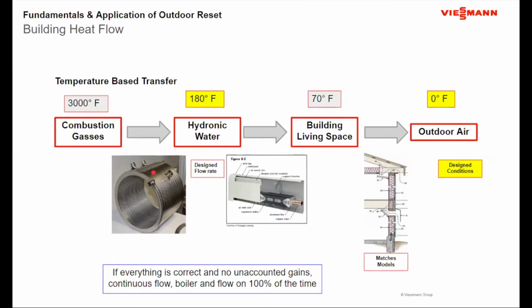Okay. And from an aspect of design, if everything is designed right, on a 0-degree day, 180-degree water, I'm putting the right amount of energy into that building that the boiler and the pump, the flow rate, everything is running at 100%. The exact amount of heat going in as the exact amount of heat going out, and everything stays balanced. And again, this is under ideal type conditions with no internal or external gains that aren't accounted for.